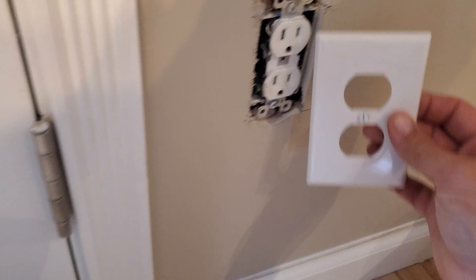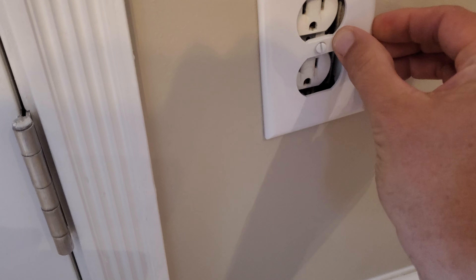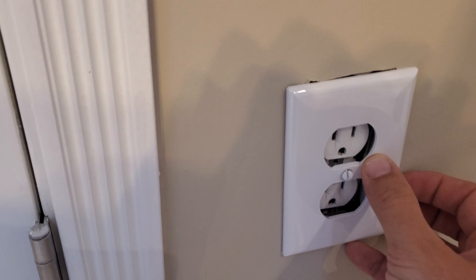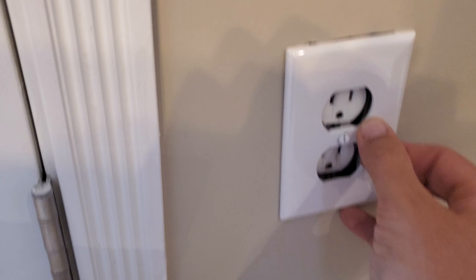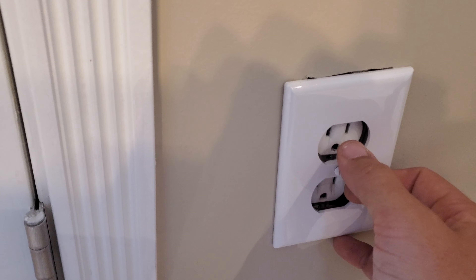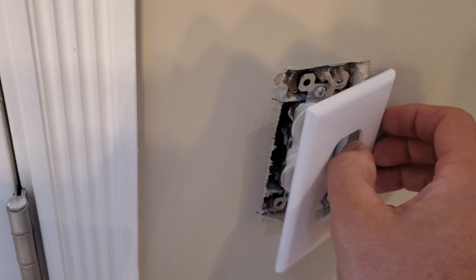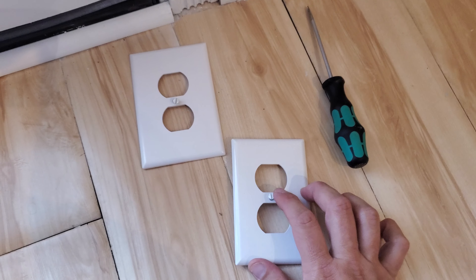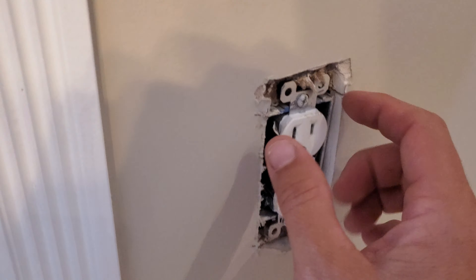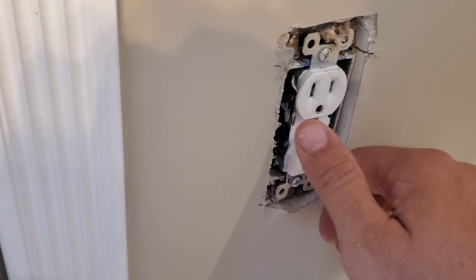If you take your standard size cover, it's not going to fit. See how far your actual outlet is recessed back in there — you would have to really screw that thing down and likely break it, and it just wouldn't look right.